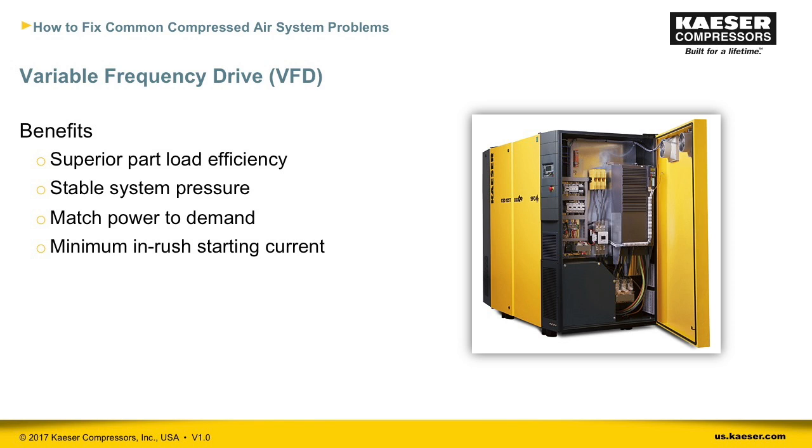Let's begin with VFDs. Variable frequency or variable speed drive is a technology that's becoming more and more popular. And it's easy to see why. It provides excellent part load efficiency and stable system pressure. It does this by matching power to demand, so it varies the speed of the motor so it can accommodate changes in compressed air demand. Additionally, it has a minimum inrush starting current, so it has less wear and tear on the motor and drive system.